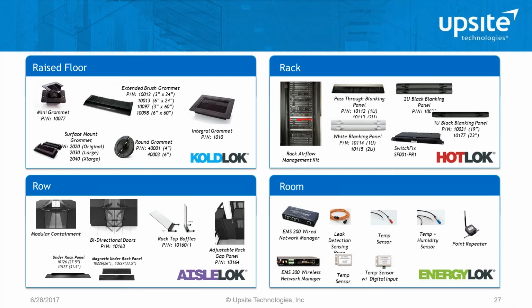In the rack line, the HotLok line of products, we have a new product called the SwitchFlx, which ducts air from the face of cabinets back to either side intake or front intake switches that are often mounted on the back rails of cabinets. These have been very problematic for a lot of people trying to improve efficiency. Then, of course, our AisleLok line of products addresses airflow management at the row level. All of these attach magnetically and are extraordinarily simple and flexible for changing environments. They can be installed in a room that is under the process of getting improved.